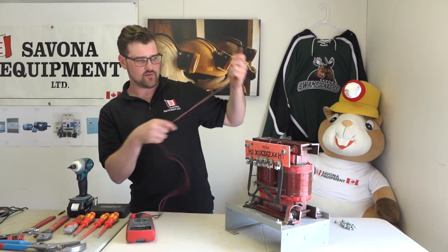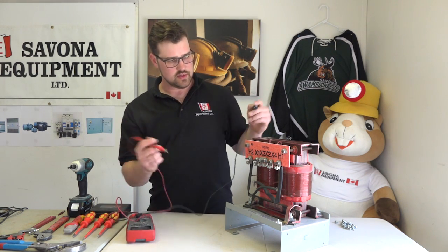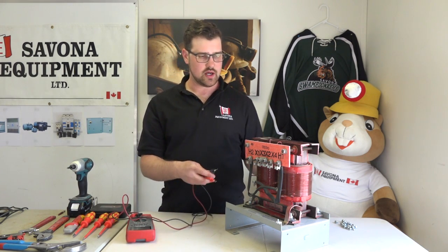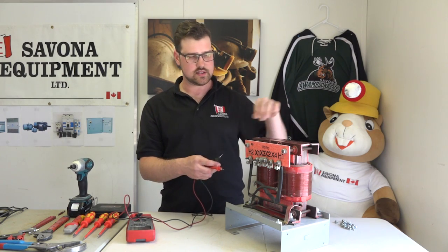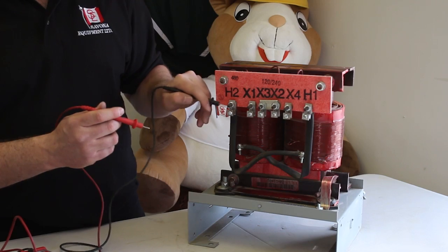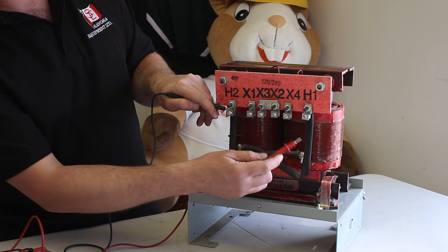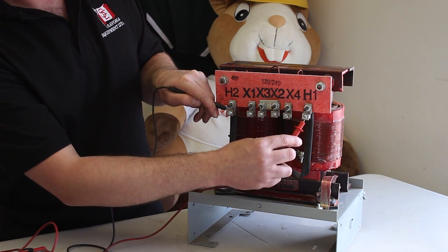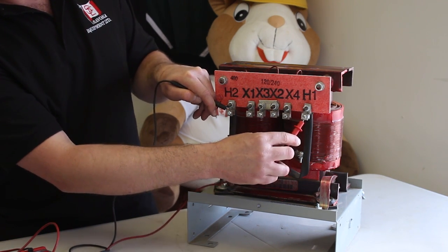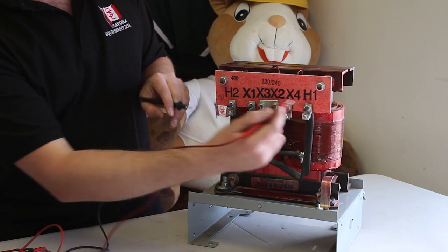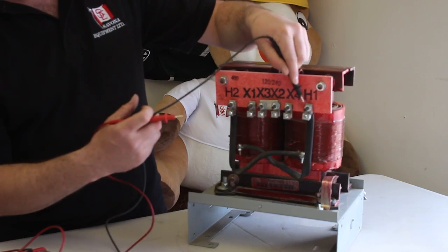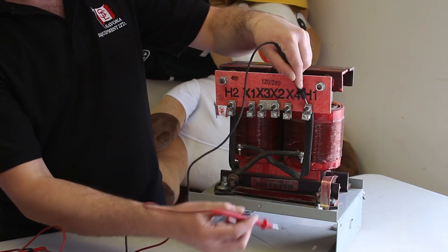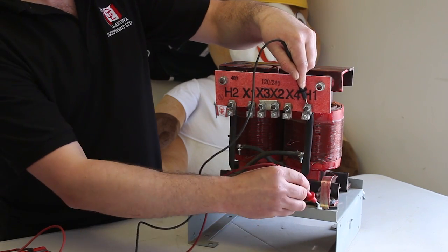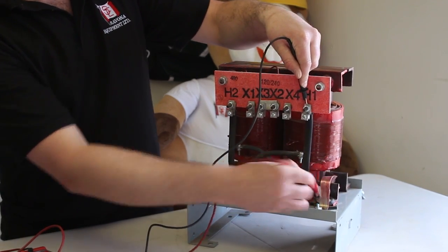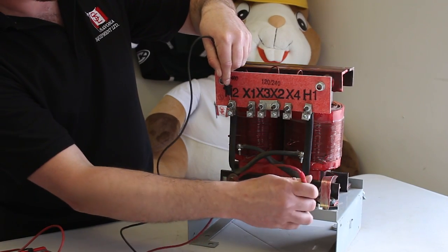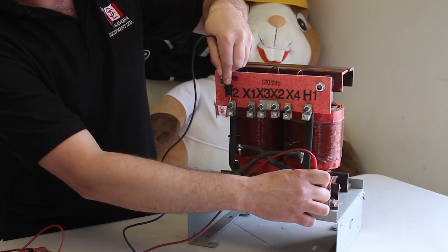So on this transformer, because the high voltage winding is connected together, you should have continuity through the high voltage winding. So we'll do that first, H1 to H2, and it's ringing through. And then we'll check that the high voltage winding to ground, or the Y connection, there's no continuity. And it's checking through as well. So I'll do the H1 and H2, and that's good.